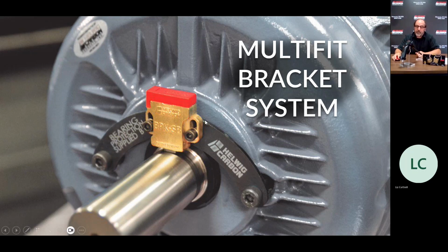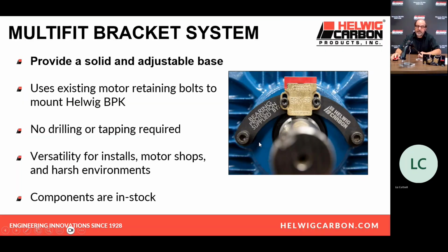It's really kind of a clever design, and again, it prevents you, especially for OEMs or motor shops, from having to drill and tap. You don't have to, no conductive epoxy, no special preparation of silver on the shaft, nothing. Existing bolts, loosen, install, tighten, walk away. Okay, no maintenance, no installation headaches.